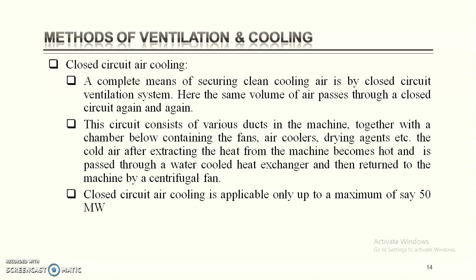Closed circuit air cooling is applicable only up to a maximum of 50 megawatt. For machines of higher rating, a large volume of air is required, and it has to be circulated, requiring hundreds of kilowatt of fan power. Because of this alone, there is no scope of increasing the rating to cope up with the increased losses.